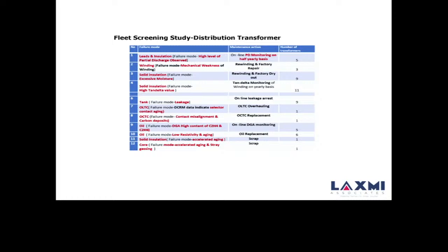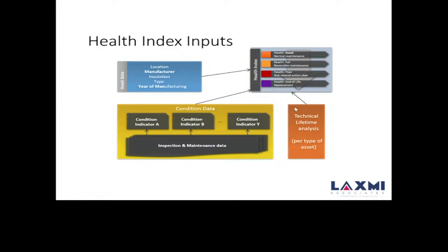Then the tank has leakage, the OLTC shows its own indication of selector contact aging. The oil has its own aging because of stray gassing, and the oil has its own life ending because of low resistivity, aging, and low DP. The core has its own stray gassing, and accordingly there's some maintenance action required.